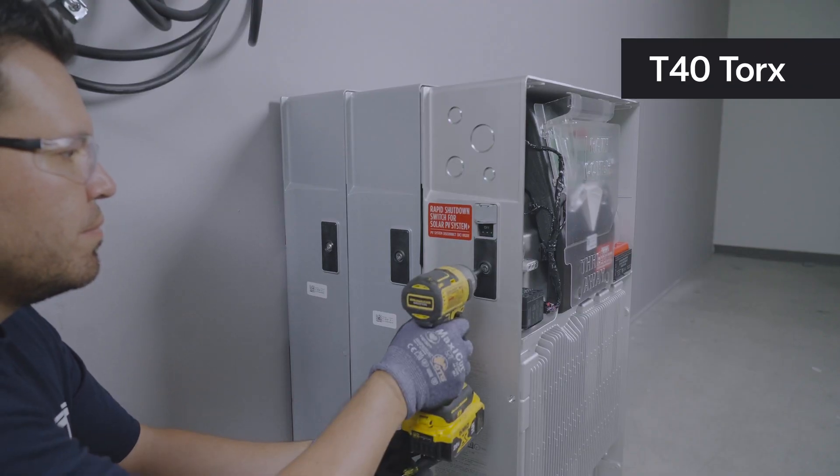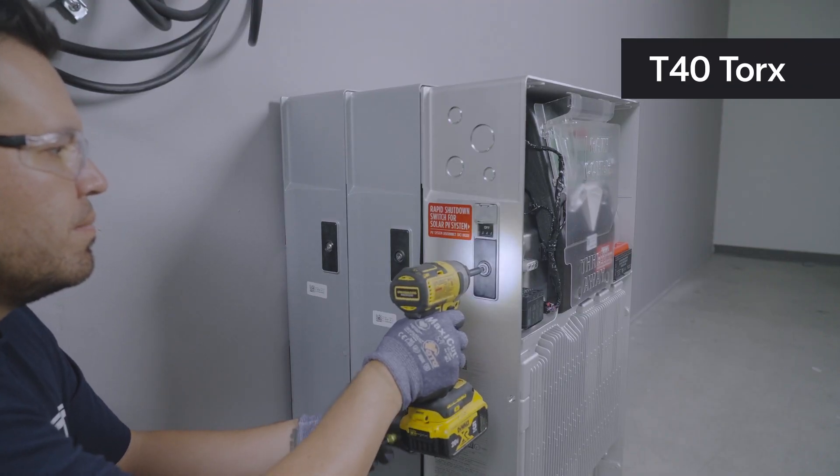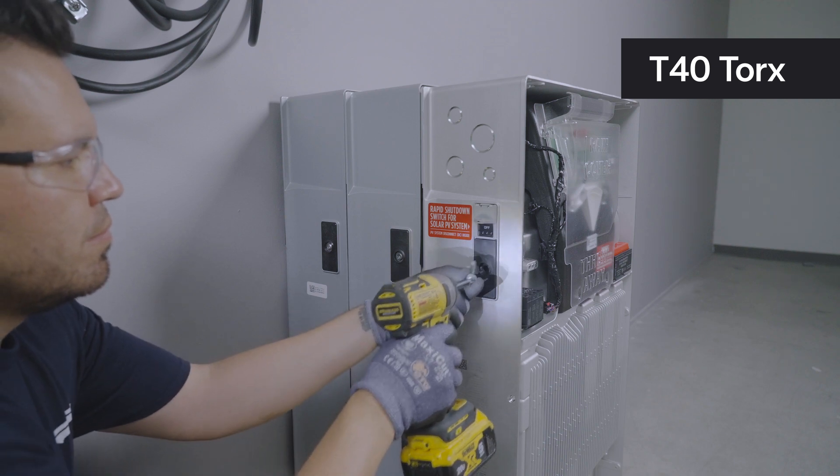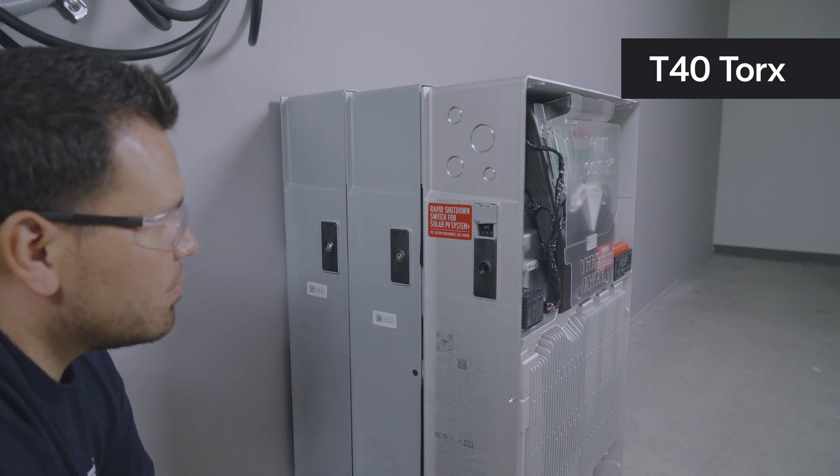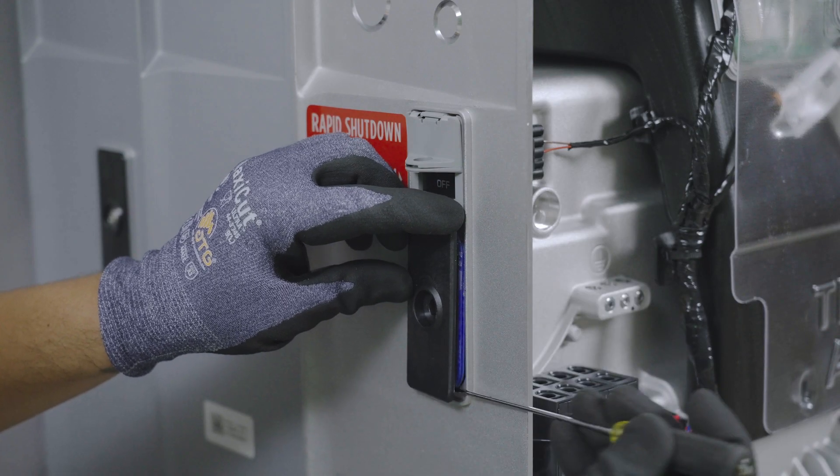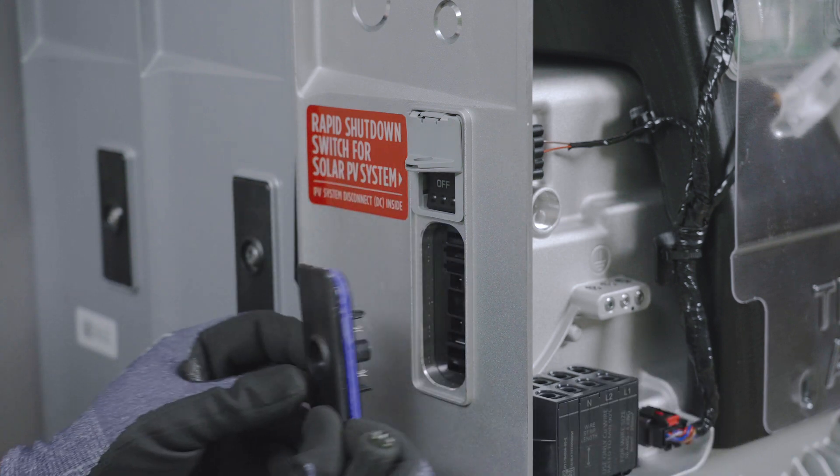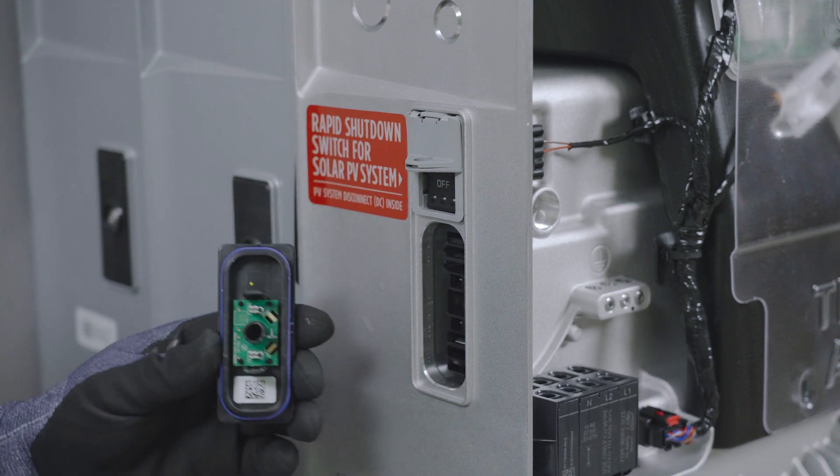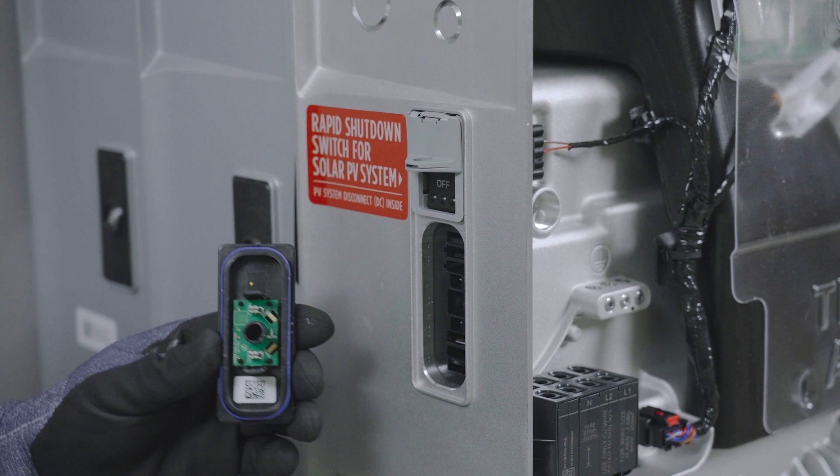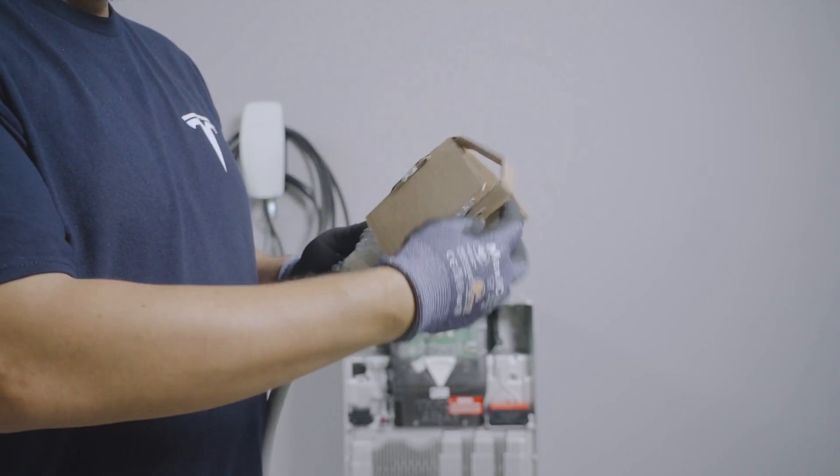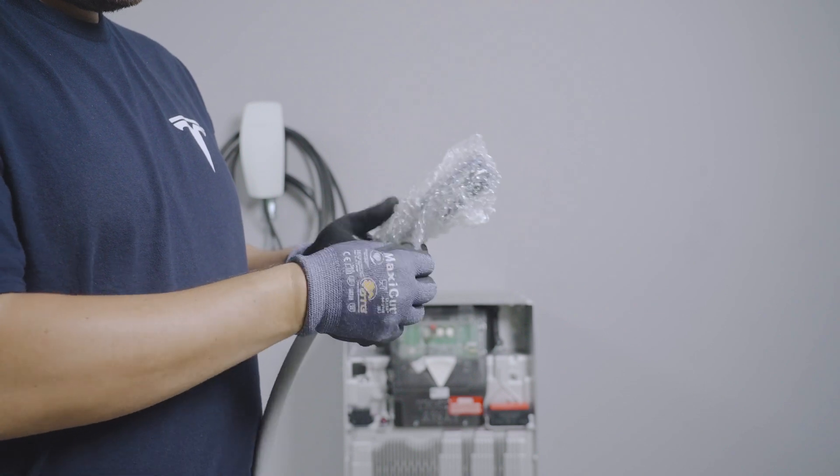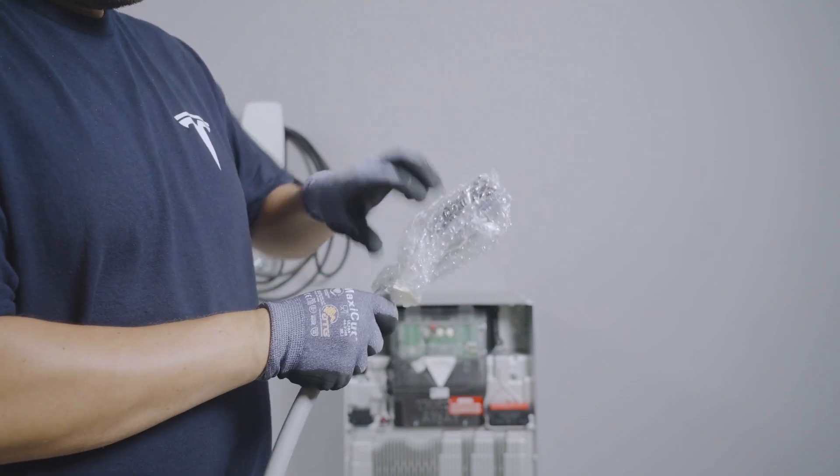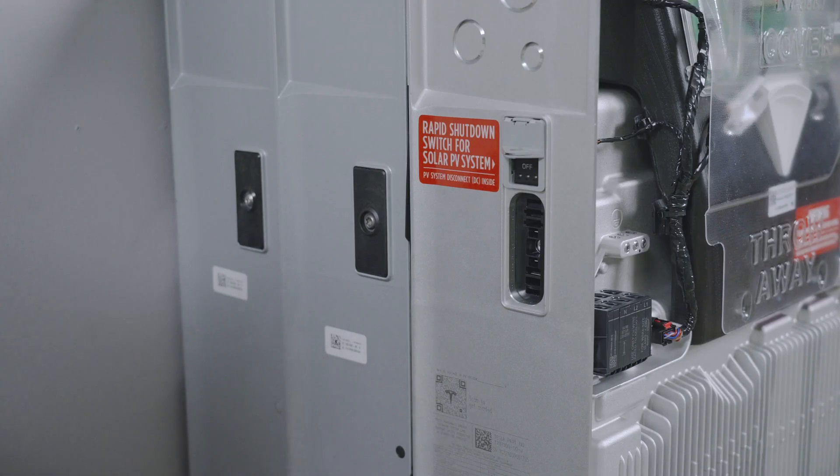Access the expansion port by using a T40 driver to remove this screw, then remove the expansion port cover. It is normal to hear the unit depressurizing during this step. Caution: do not remove this cover if exposed to active rain or snow. To prevent damage or debris, do not remove the protective cover from the wiring harness or the expansion port cover until ready to make connections.